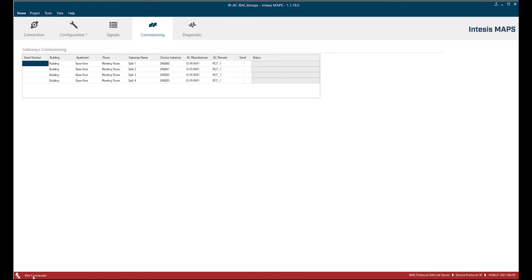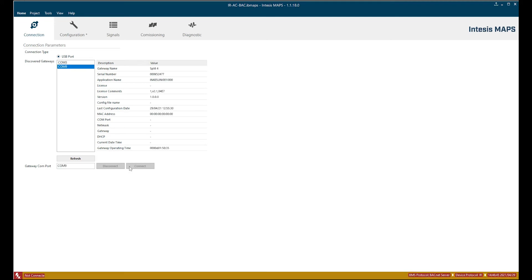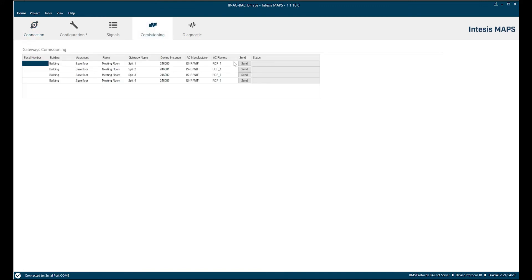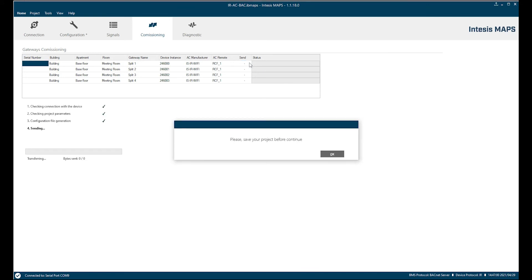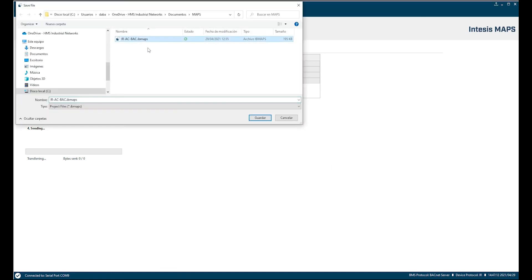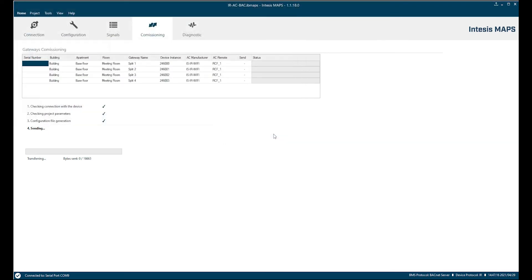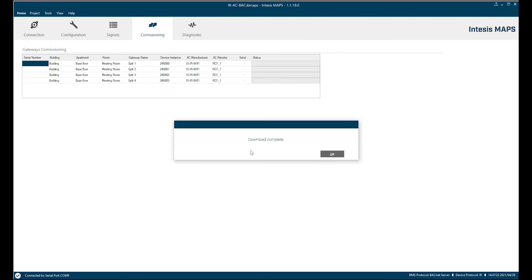Here on the left downside we see that we are not connected to any device. I'm going to connect it. I go back to connection and here I have connected one device on COM 8 via mini USB. I connect this device. I go back to commissioning and here the send buttons appear. So I'm now going to send the configuration for the first split into my gateway. First thing the MAPS will ask me is that I need to save my project. Okay, let's do this. I have here already a project which I'm going to use for that and you see the downloading starts and it notifies that it's complete.